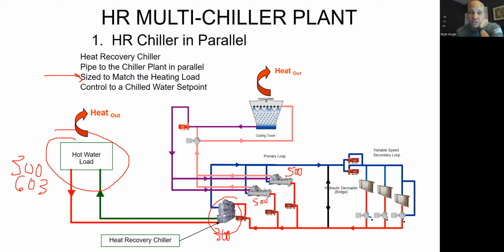So maybe this 300 tons represents my domestic load, right? Showers and hand washing and laundry, and maybe at the hospital, they have all kinds of needs for hot water and stuff like that. And then it could need more hot water for heating the perimeter of the building at different times of the year. But what's my baseline? That's what I'm going to size it for. So this guy just constantly shoves heat between these two things. You want heat, you want to get rid of heat. Perfect. Let's marry you guys up.